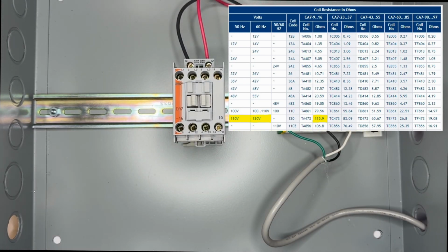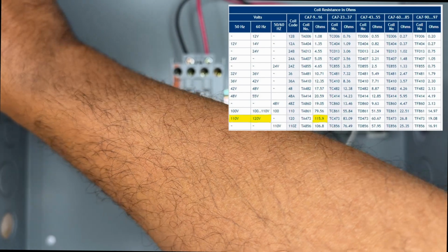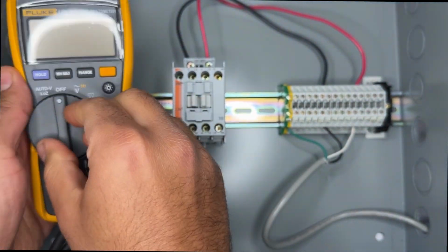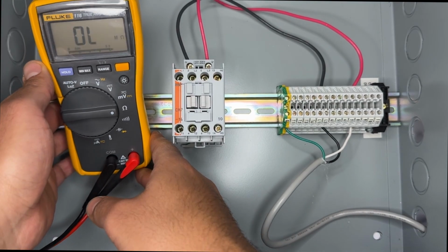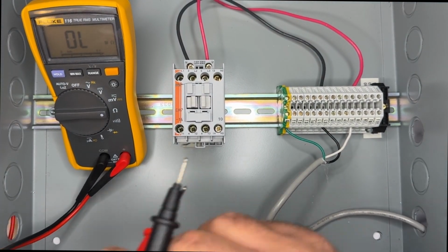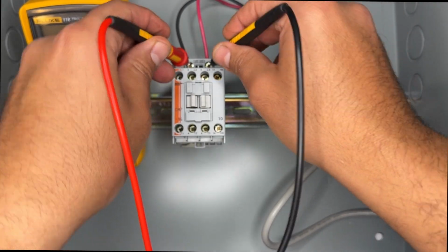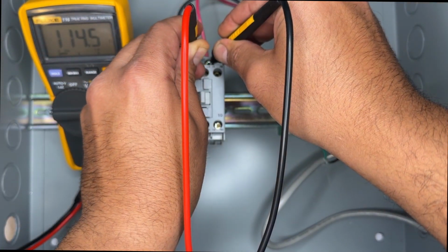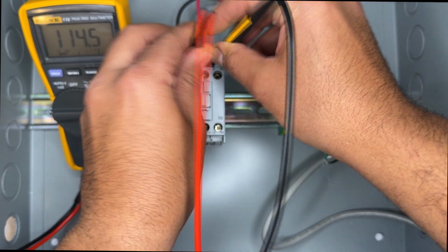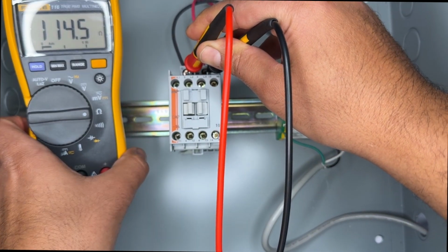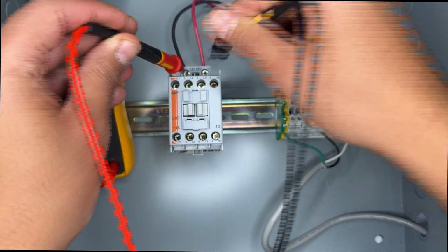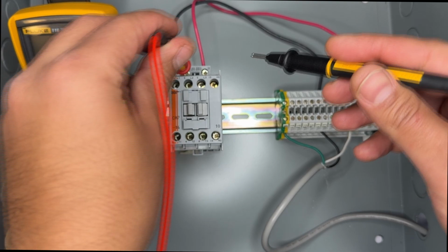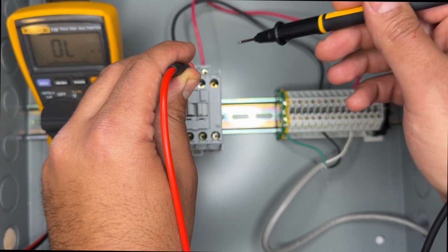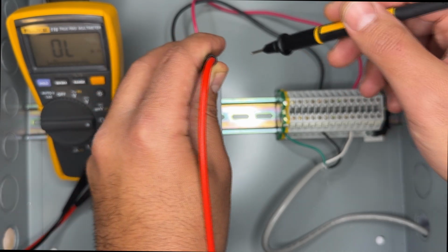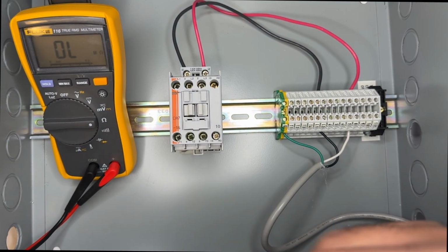Now you want to make sure that you have no power applied to your panel when you're doing this. And let's bring our multimeter over here. We're going to set it to resistance, and we're just going to put one probe on each end of the coil here, and let's see what we get. 114.5. Now that's quite close, so that tells me that this coil is in good shape, at least as far as this test goes. Now if that value is really low or really high, for example, if you see it's open like this, that would indicate that you have a faulty coil. But this one is reading just fine.